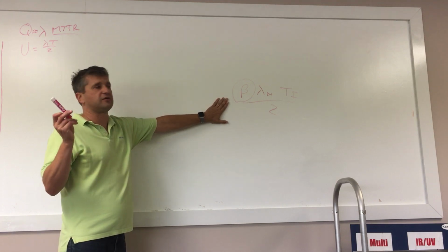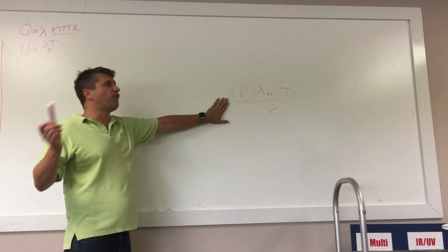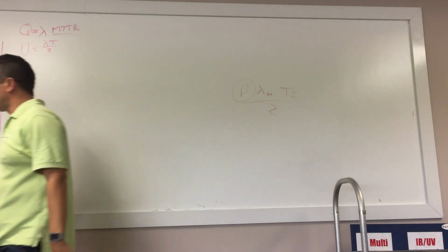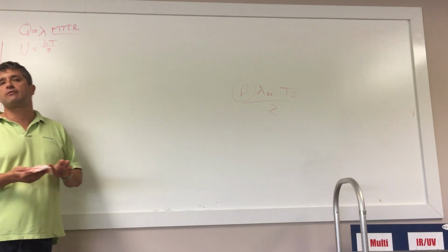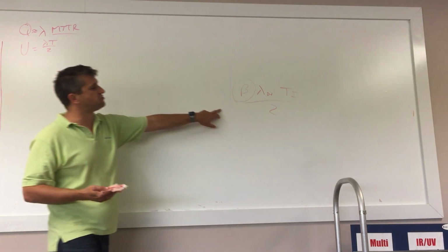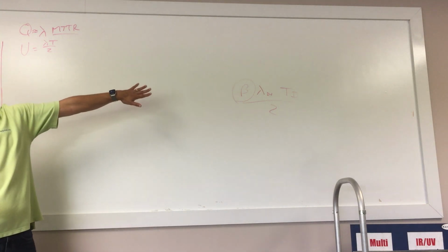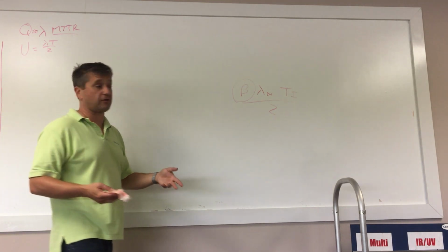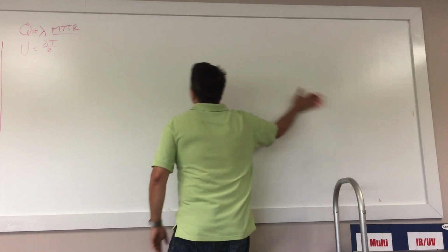So this beta factor term is going to be applied uniformly, whether it's 1 out of 2, 2 out of 3, 1 out of 3, 1 out of 4, 2 out of 4. You're always going to be beta lambda t over 2. And in the more sophisticated voting arrangements, this term is going to generally dominate, to where if all you calculated was the beta factor term, you would be close enough to the actual answer that you could ignore everything else. So that's the driver.